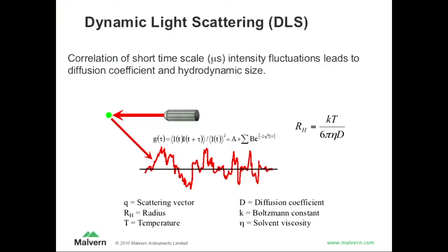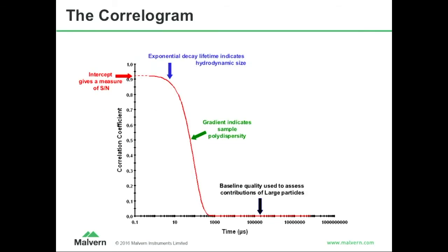And then the rest is just theory. The exponential decay rate of that movement is related to the diffusion coefficient, and then you can use the Stokes-Einstein equation to get the hydrodynamic size out of that. You just need the Boltzmann constant, the thermal energy, and then the viscosity. If you pay a little closer attention to the equation, there's actually a summation of different exponential decays, because in real life things are a little more complicated. If we have just one particle kind in the sample, you can measure a correlation function that ideally has a nice intercept — meaning the y-axis is close to one — giving you an idea of the contrast between particle and background. Where the function falls off, indicated by the blue arrow, gives you an idea of the timescale. You can look at the slope on a linear y-axis, logarithmic x-axis plot — it looks like a sigmoidal curve — and at very large times you can look at the baseline, which tells you if there are really large, very slow things in there.